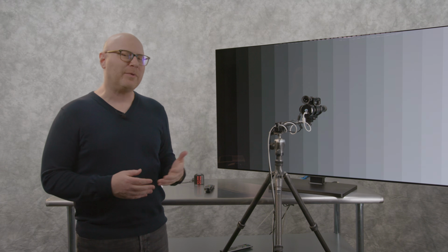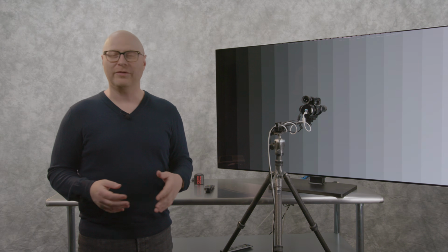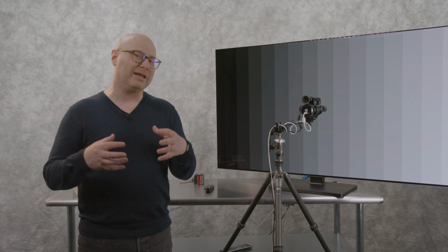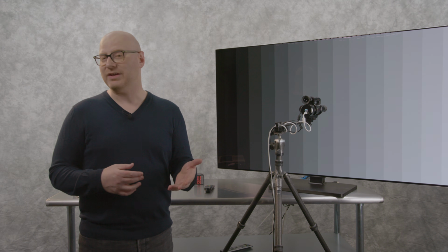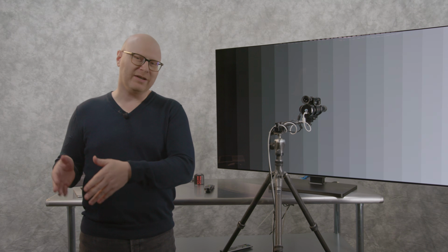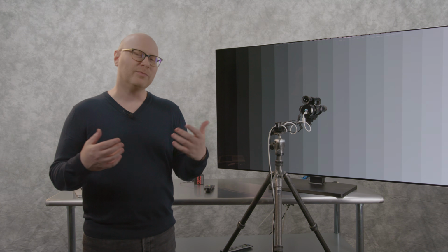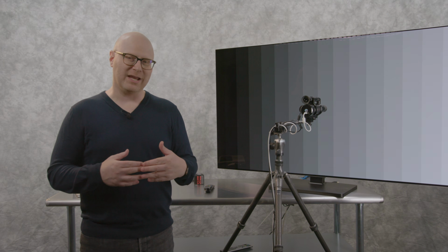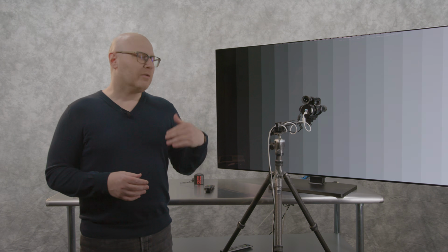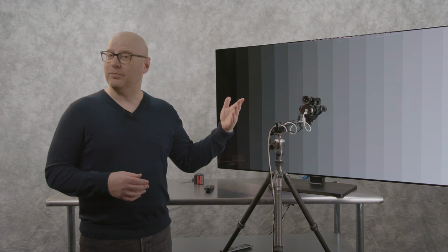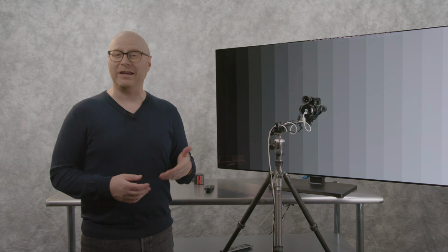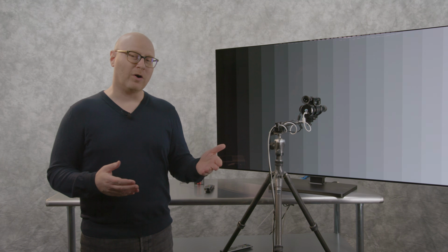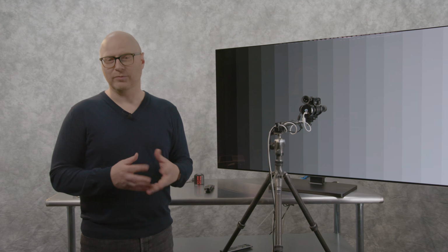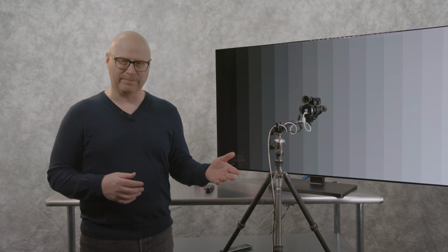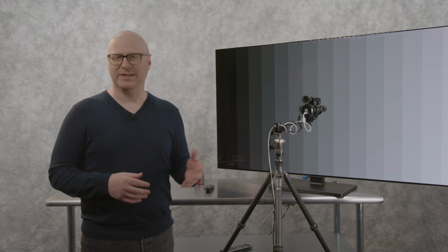Now it's important to note that both the LG OLED and the Calman machine have to be on the same network. If they're not on the same network, you might have to find a way to get them on the same network. If you're running a VLAN where your computer's on one segmented network and the LG's on the other, you'll have to bridge those together or put them on the same. The other thing to note is that Calman is communicating over certain ports. If those ports are being blocked by antivirus software or a firewall, you also may need to remove those in order to perform the calibration. For most people though, we find this isn't an issue.